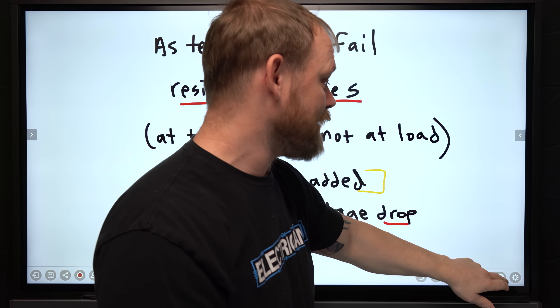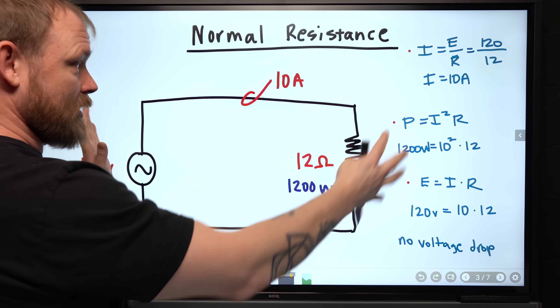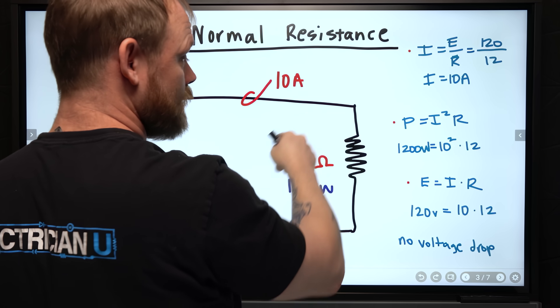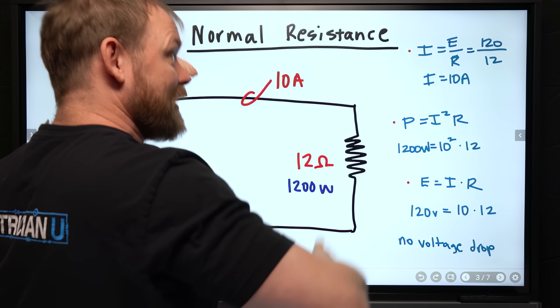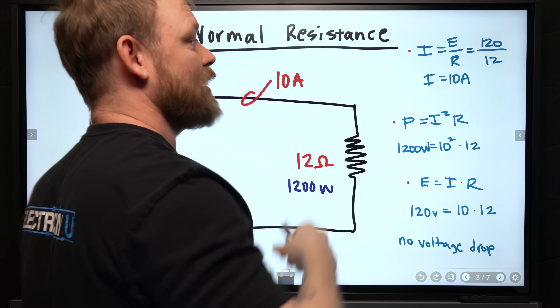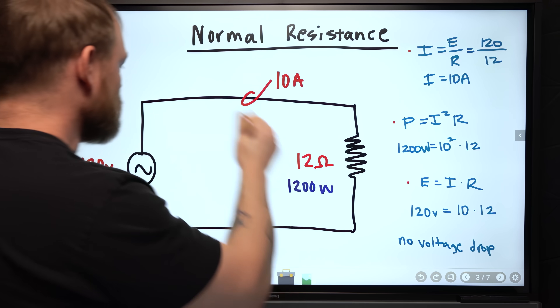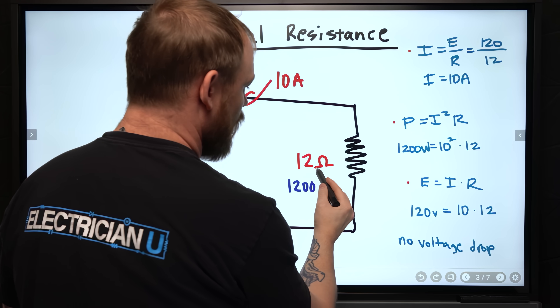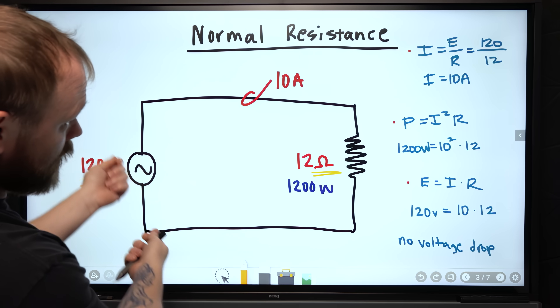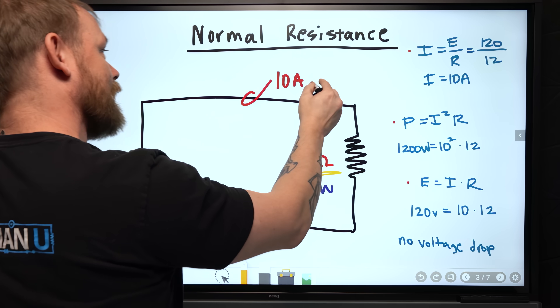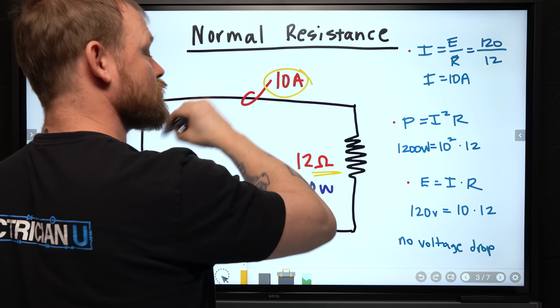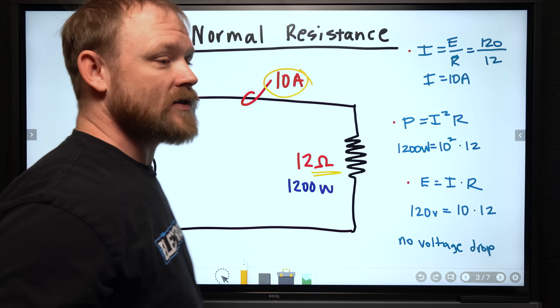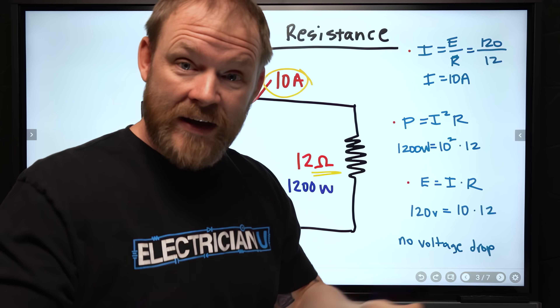Let's break into the examples. We're going to go from normal resistance, raise resistance at a termination, keep raising it, and see what happens. In this situation we have a 120-volt circuit with a 12-ohm resistor. When we bring 120 volts across 12 ohms, 10 amps naturally flow. The heat dissipation is 1200 watts — think of a 1200-watt space heater.